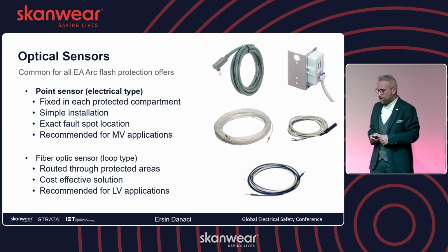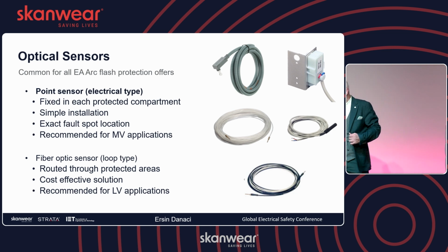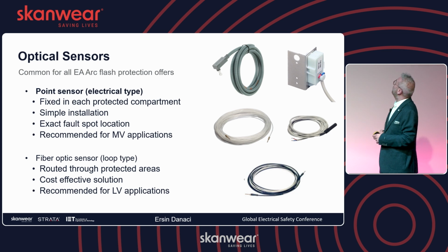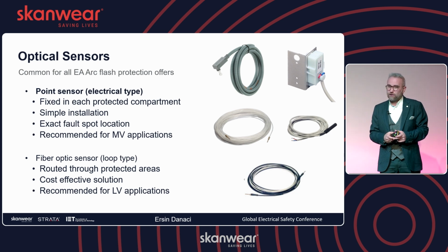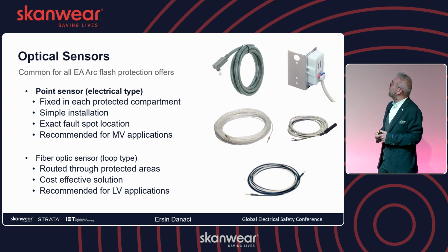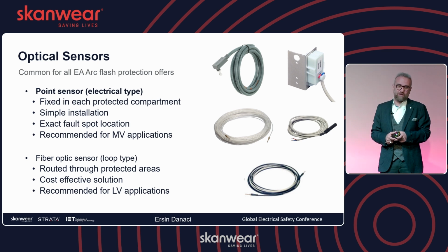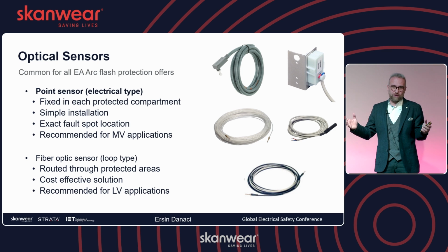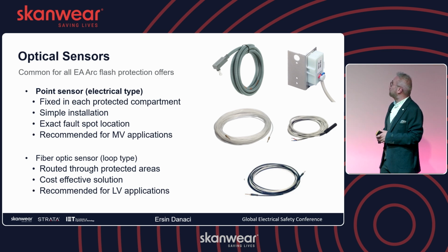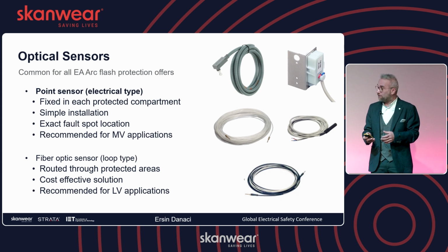So on this slide, we see various optical sensors. As you can see, we have point sensors on the right corner, and we also have the fiber optic loop. The difference is that point sensors we utilize more in MV applications, because they are easy to install, especially for retrofit projects as well, and also quite easy to set up with the application. Whereas the fiber optic loop we use for the LV switchgear, because we will have more sensors, and it will be cost effective to utilize the fiber loop in LV switchgear applications.